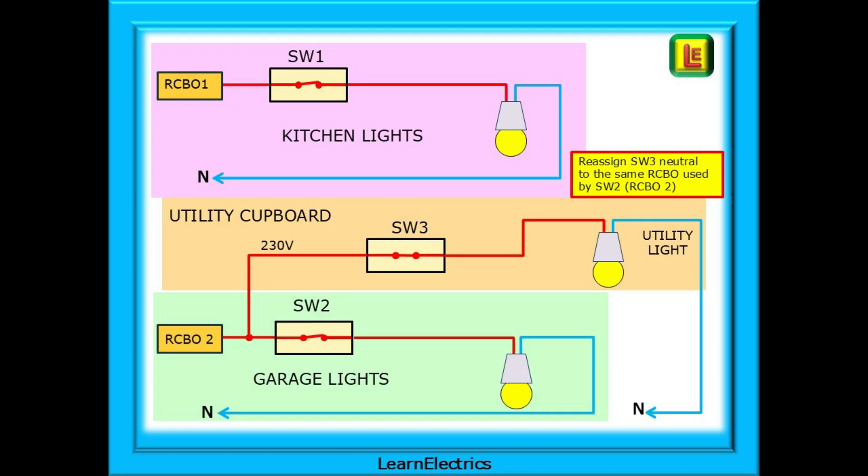The problem was easily put right. We reassigned the utility room neutral SW3 to the same RCBO used by the garage circuit, which is switch 2 and RCBO 2, and all was okay. It would have been possible to reassign the line conductor for SW3, the utility room, to the RCBO for the kitchen lights. Either way would have worked.